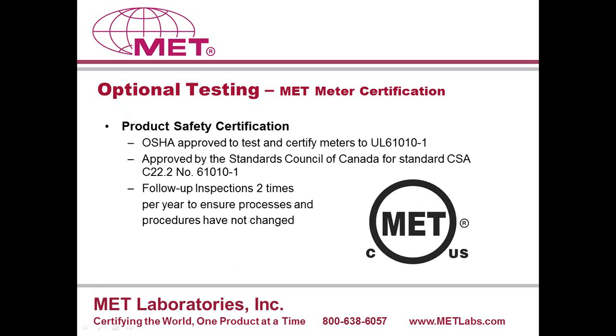really. Getting into the details, quickly, the product safety certification or the listing: OSHA approved testing to UL 61010 for metering products. Not necessarily a requirement in all jurisdictions, however your buyer may request it or require it of you. In these cases, a listing is going to be like any other product safety listing, 60950 for example, where not only are we evaluating the product and giving you a MET mark, allowing you to mark your product as listed by MET Laboratories, but it would involve follow-up inspections to make sure quality is in process and available at the manufacturing facility. Things are up to snuff there in terms of what is required for that product listing.